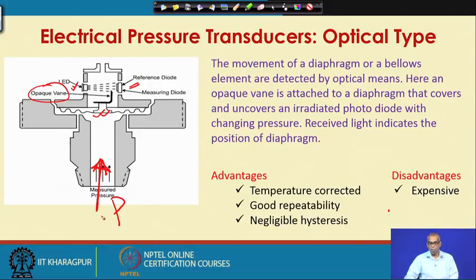So, the movement of a diaphragm or a bellows element is detected by optical means. Here an opaque vane is attached to a diaphragm that covers and uncovers an irradiated photodiode with changing pressure. Received light indicates the position of the diaphragm, and the position of the diaphragm is a measure of the pressure. So, the output of the photodiode can be directly calibrated in terms of pressure units. We have certain advantages of using optical type electrical pressure transducers, such as temperature corrected, good repeatability, negligible hysteresis. However, they are more expensive pressure measuring instruments.